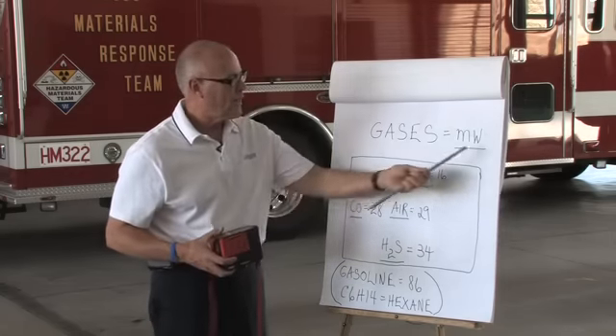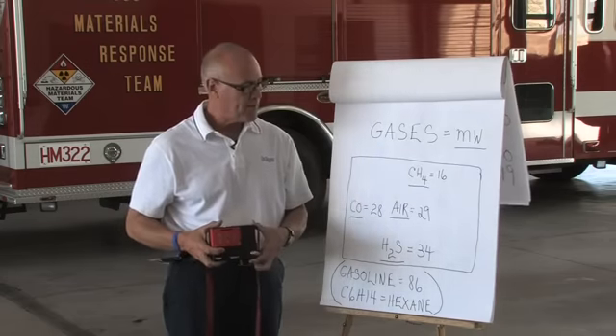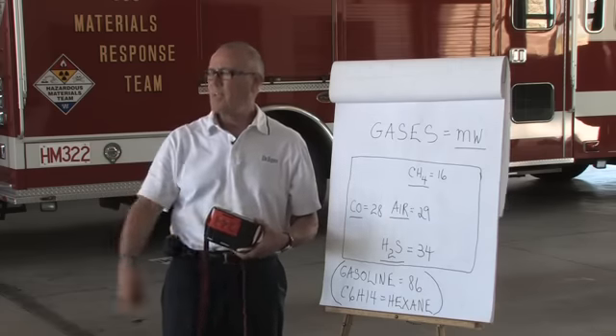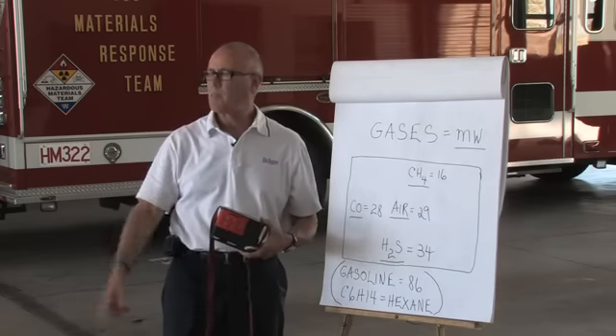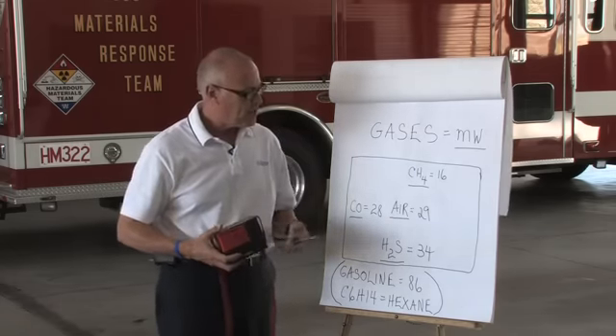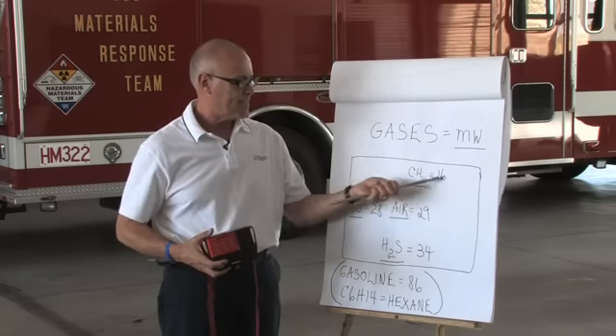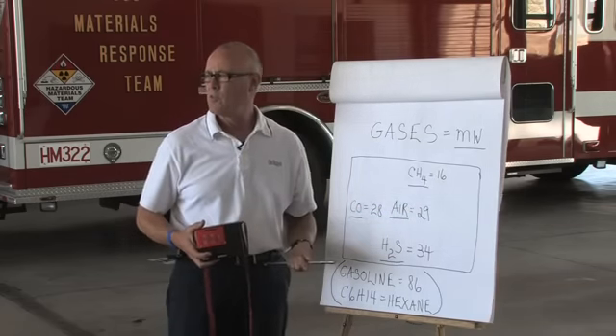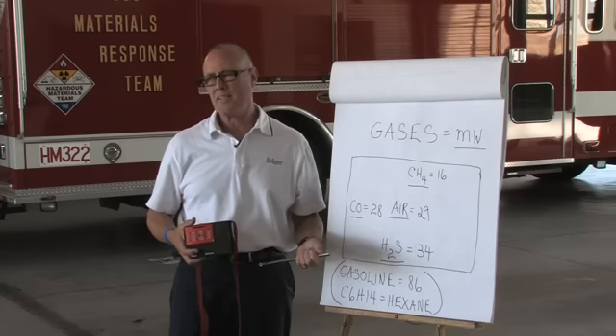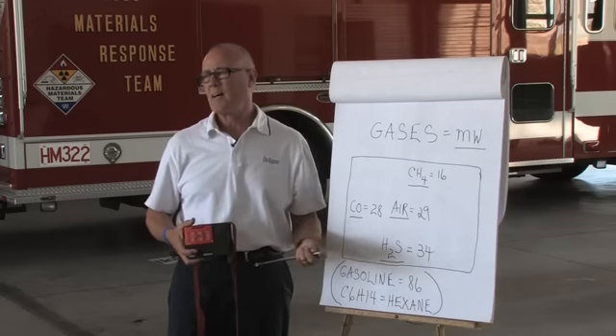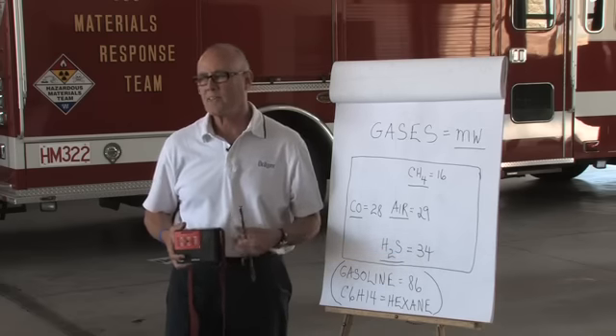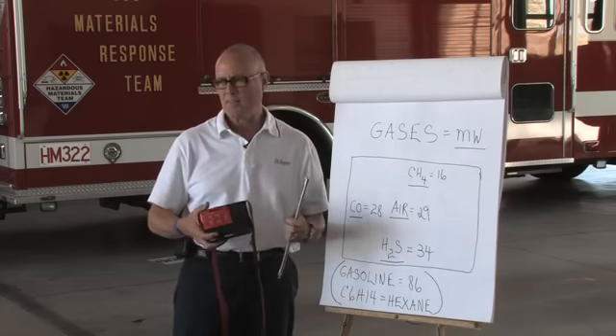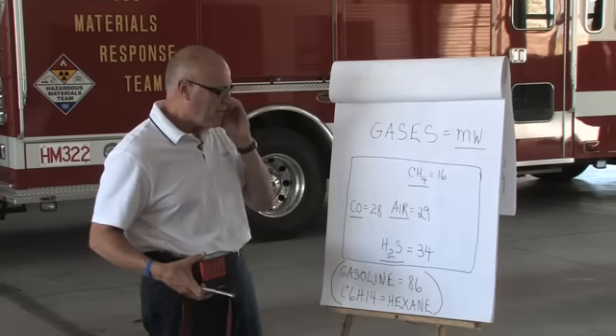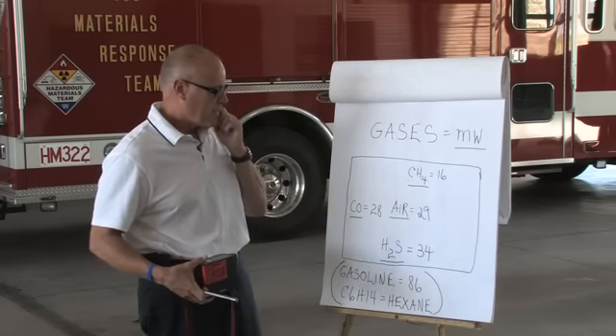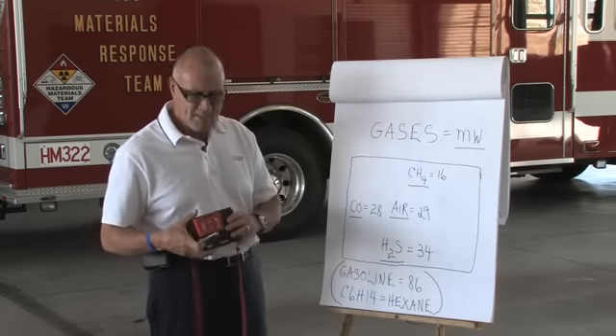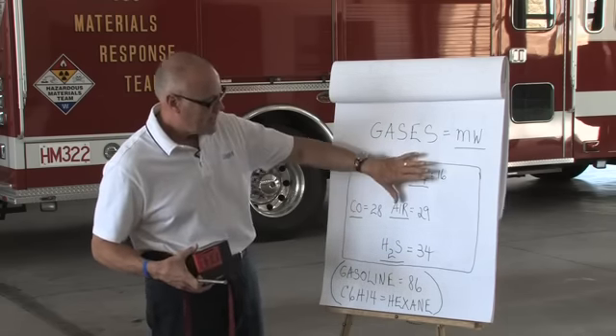So molecular weights play a big part in this, but remember, convection and air movement mixes all the gases up as well. And you have to have pretty high concentrations, again, to get your natural gas readings to move. Because you're dealing in a lower explosive limit scale, not a parts per million scale, which would pick up minute traces of natural gas.